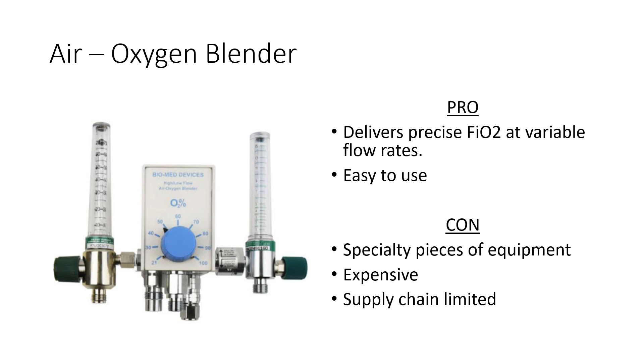But if you have access to compressed air and compressed oxygen, you can mix those flows without a blender and still give precise FiO2s. And these are just 3 adapters I found in the back room of our equipment supply area, just to figure out a way to mix these 2 gas sources. And to the right there, we have a high pressure pop-off valve. Those are easy to come by. It's a manifold, so the pressure can't inadvertently build up. I mean, granted, we practiced high flow therapy for a very long time without high pressure manifolds.